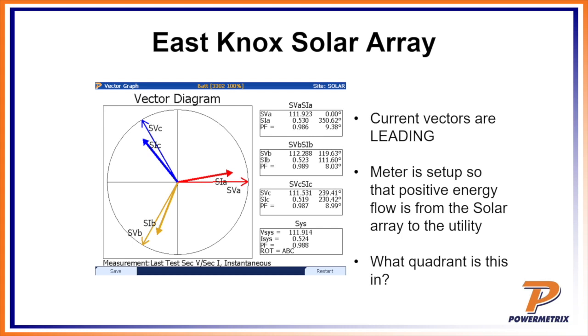Okay, that's fine, but I think it's confusing to someone coming out to do maintenance on the meter. This is a leading power factor, notice that it's shifting up. Again, they rewired this site to always look as if it's in delivered mode, which is not really—it's actually in received mode.